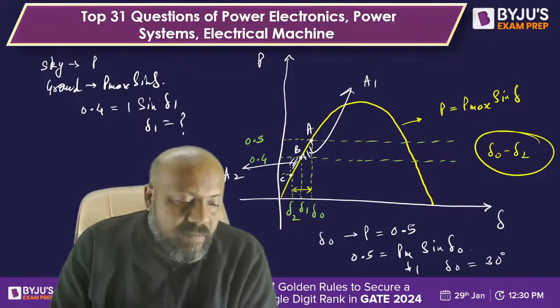Listen, listen, he is asking the power factor of the synchronous motor, that is the synchronous phase modifier. He's not asking the power factor of the induction motor. The power factor of the induction motor is already fixed. You can never ever change the power factor of a motor once you design it, it's fixed. You can't change it, you can only improve the system power factor.